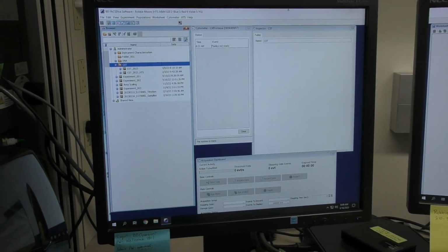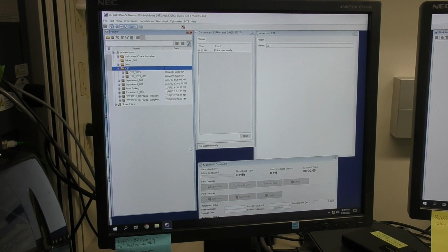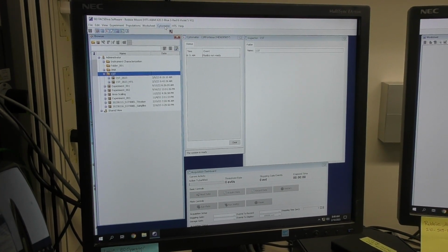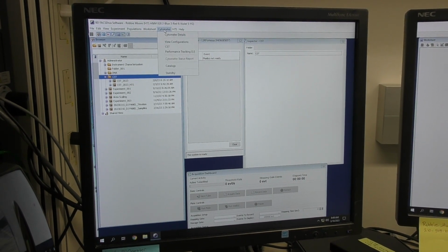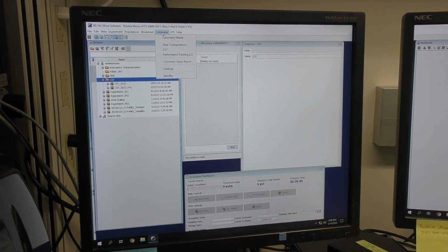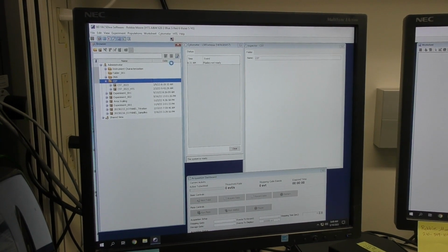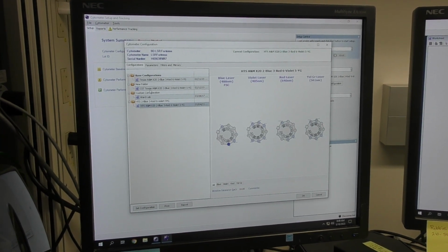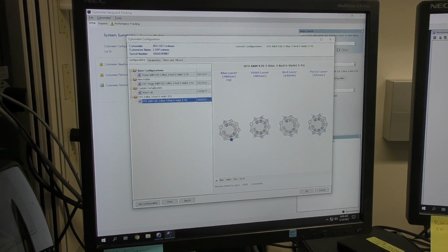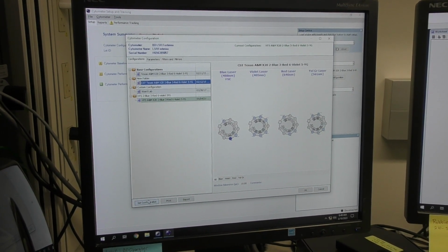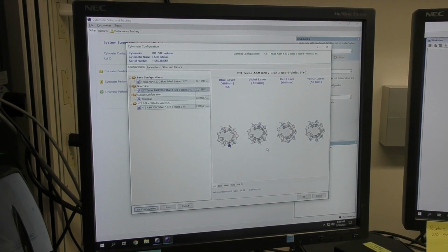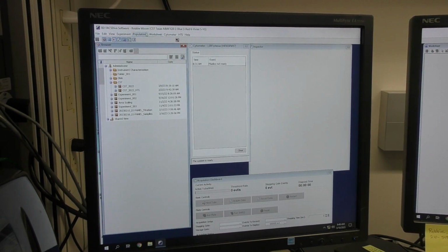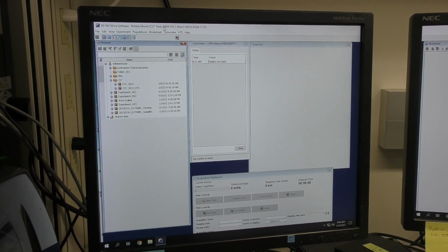Now we're going to switch the Fortessa from plate mode or HTS mode back into tube mode. The first thing we want to do is switch the configuration. So go to Cytometer, View Configurations, and choose this one, CST A&M, Set Configuration, OK, OK, close out of this window, and we can see that is no longer in the HTS configuration.